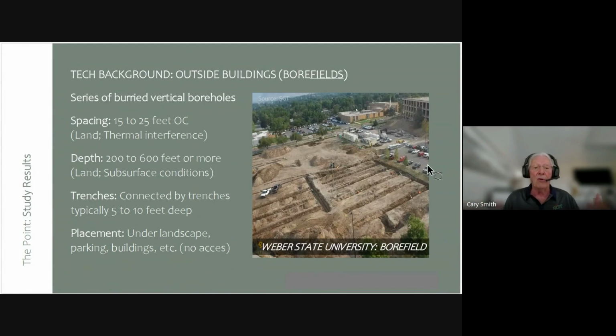How about vertical boreholes, spacing 15 to 25 feet, depth about 200 to 600 feet. These are closed loop holes in the ground with plastic pipe in them, high density polyethylene, and they are grouted with thermal grout to aid in the heat transfer. We have to put trenches in to connect these, obviously, but they can be placed under landscape, parking, buildings. It doesn't matter what it is.